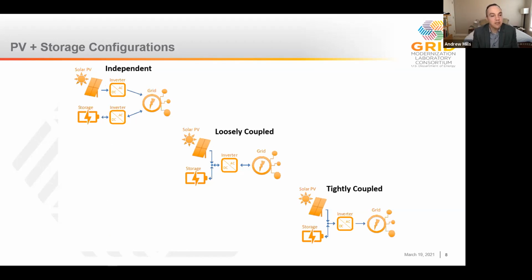The systems could be completely independent, connecting to the grid without interacting with each other directly. Alternatively, they could be brought together with shared infrastructure, such as a shared inverter or a limited point of interconnection. This loosely coupled configuration shares an inverter but still allows storage to charge from the grid or from the solar. A tightly coupled configuration restricts the storage to only charging from the solar.